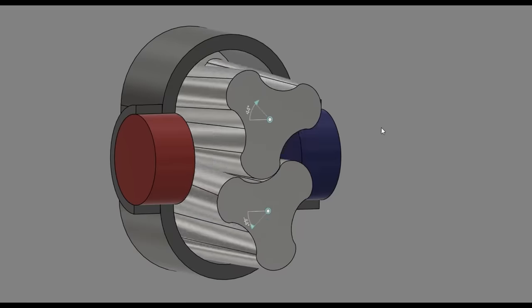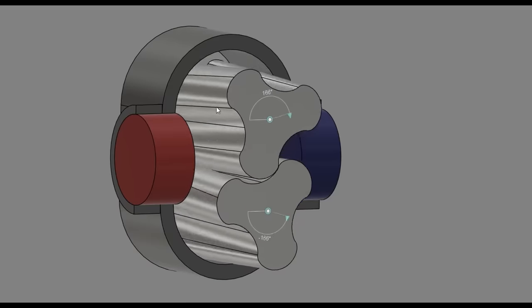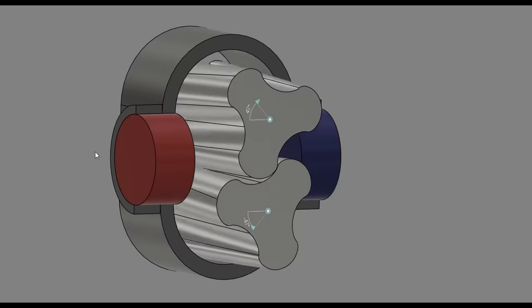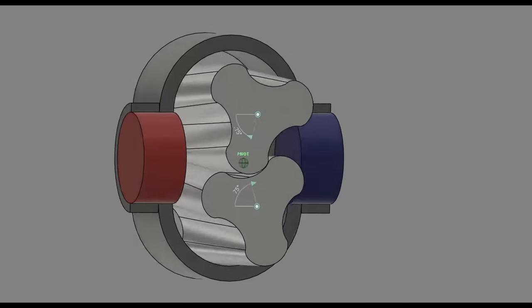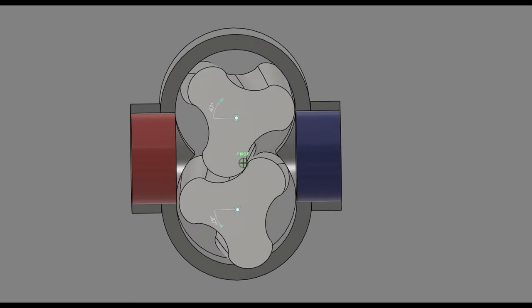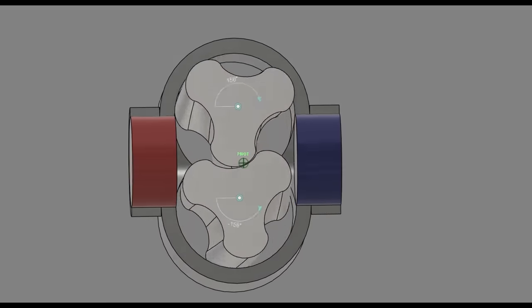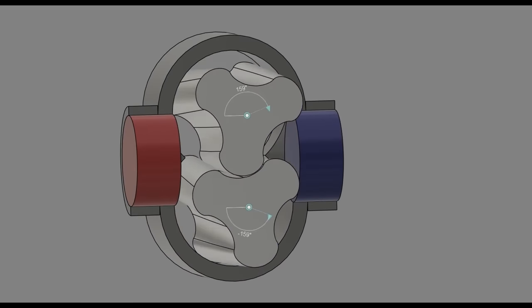Almost all of the time, the rotors are symmetric and have the same number of lobes, and a Roots style blower might have a slight twist angle to the rotors, maybe 10 to 15 degrees, which might confuse some people. That's only there to reduce the pulsation of the air, making the compressor quieter.